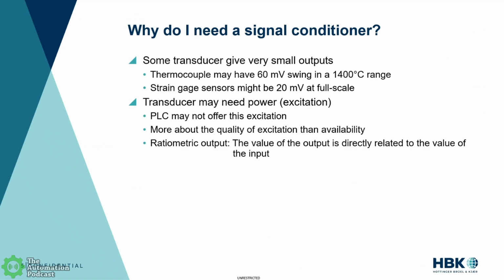Transducers might also need some sort of power. The term we would normally use, again, HBK, we're normally talking about strain gauge based transducers, we might call that excitation. Now your PLC may or may not offer this excitation, but whether it does or not, it's more a question about the quality of this excitation than its sheer availability, right? You might have a 5 volt or 10 volt controls power source in your control cabinet.